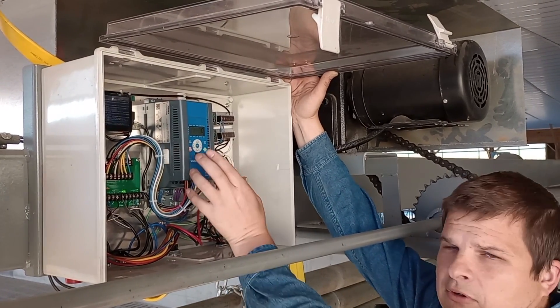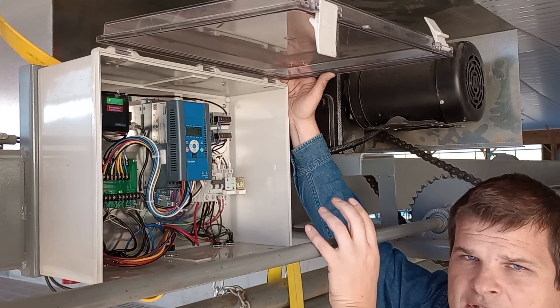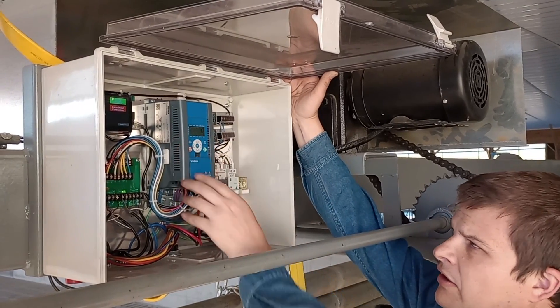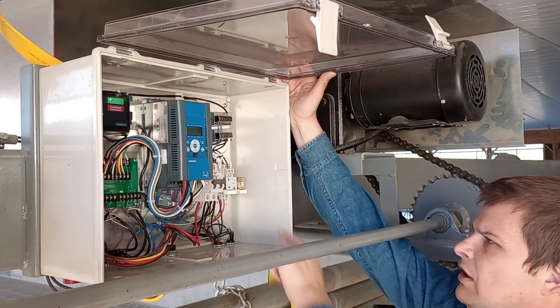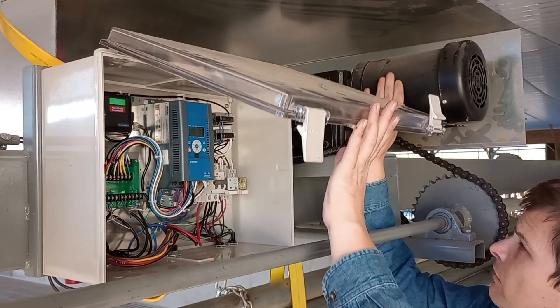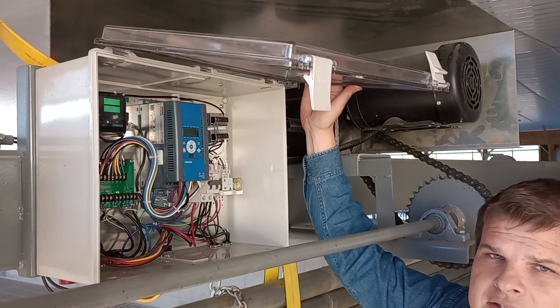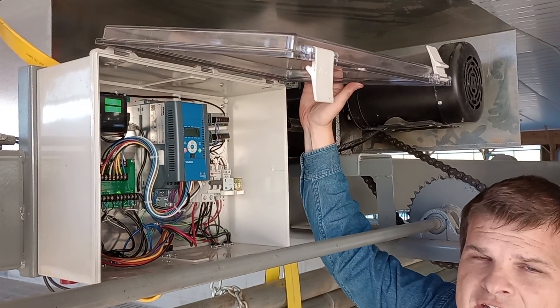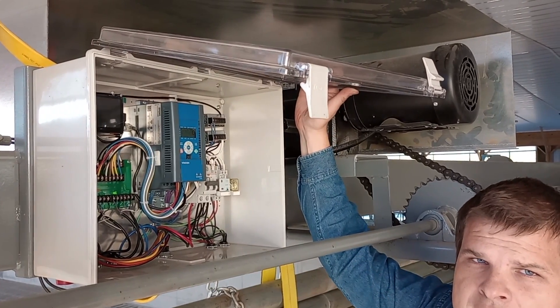This is a VFD programmed to act as a crowd gate control. It needs to be illuminated — all the brains are in here — so this unit has to be on and the breaker has to be on. This little light will come on whenever the up or down motor runs. The forward/reverse motor is right here and the up/down motor is on the other side; only one motor runs at a time, and the light turns on any time the up or down motor runs.